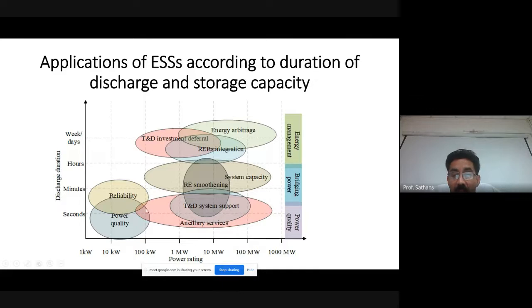For power quality applications, what's required is that the discharge time should be really less - in seconds at most, or maybe not beyond minutes. For bridging power applications, the discharge time could be from minutes to hours. And for energy management, it could extend into days and weeks. So these applications are categorized in terms of discharge time requirements.